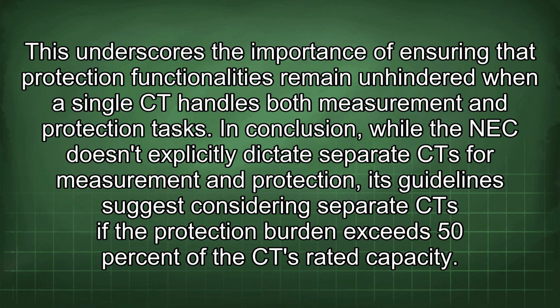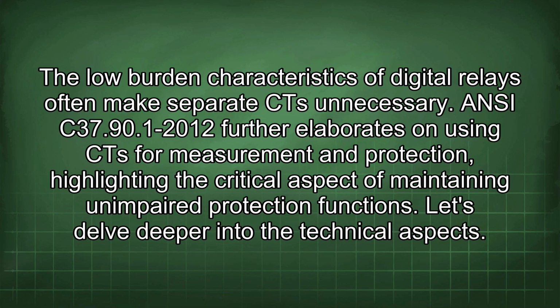tasks. In conclusion, while the NEC doesn't explicitly dictate separate CT for measurement and protection, its guidelines suggest considering separate CT if the protection burden exceeds 50% of the CT rated capacity. The low burden characteristics of digital relays often make separate CT unnecessary. ANSI C37.90.1-2012 further elaborates on using CT for measurement and protection, highlighting the critical aspect of maintaining unimpaired protection functions. Let's delve deeper into the technical aspects.